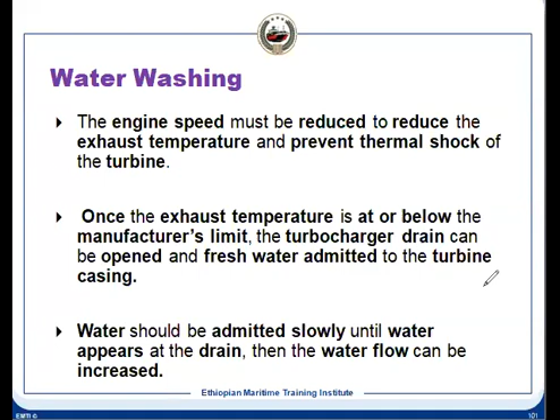Initially, the water is admitted slowly. It's not that you open the water completely. You open it slowly and check the drain, where there will be a funnel through which you can check whether water is coming out or not. Once the water starts coming out, then you increase the flow, because that ensures that the passage for water draining is open. Otherwise, water will fill up in the turbine casing and it will damage your turbine, the turbine side. So this is the way we do the turbine washing.